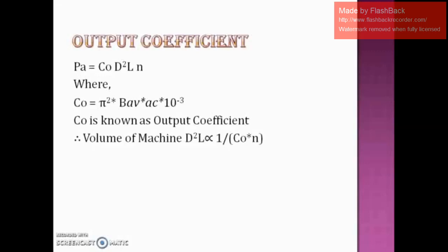The volume of the machine — meaning the volume of active parts — will decrease with increase in speed and/or increase in output coefficient. Therefore, the size and cost of the machine decrease with increase in speed and/or output coefficient. So, the volume and cost of the machine are very important considerations.